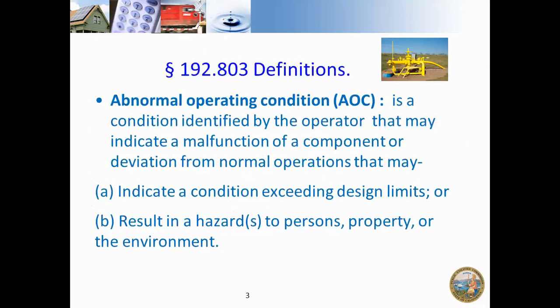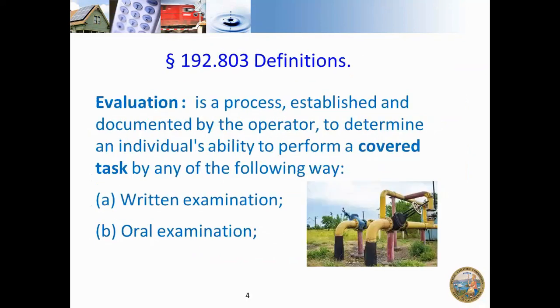Sometimes you have heard AOC — in short, abnormal operating condition. Any condition that seems to be a malfunction of a component or deviation from normal operation is called an abnormal operating condition, or AOC. AOCs indicate that there is an exceedance of design limits or result in a hazardous condition for persons, property, or the environment. These are part of the definition of covered tasks.